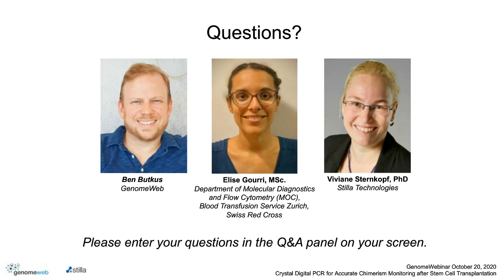The next question is for Viviane: what is the fundamental difference between your technology and chip-based digital PCR? Our chips — Opal and Sapphire — are prefilled with oil, and you apply your sample reaction mix onto them. We have a droplet-based digital PCR within a chip environment. The chip is designed so that all the partitions created within are of the same volume — essential for running digital PCR.